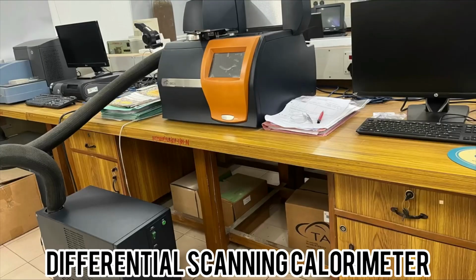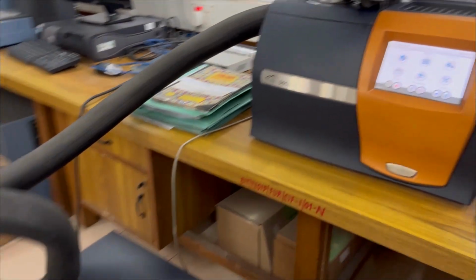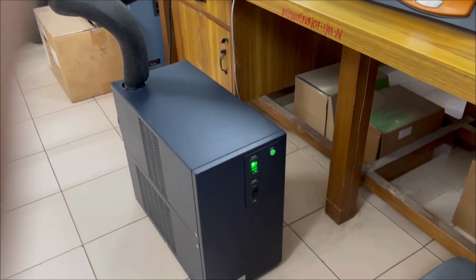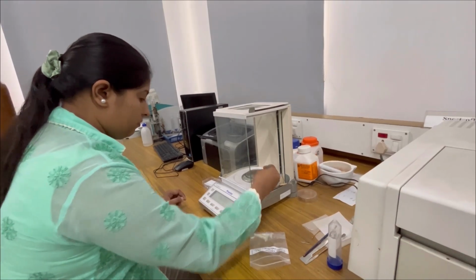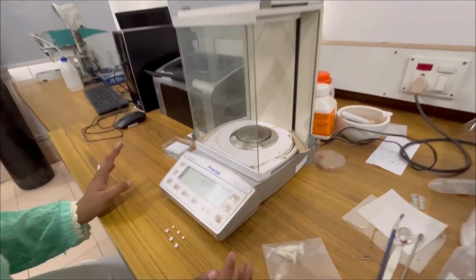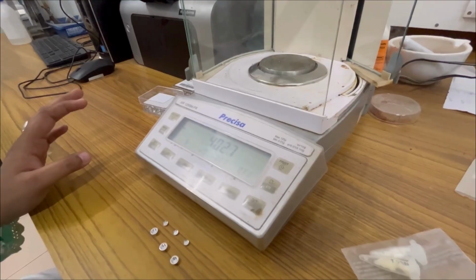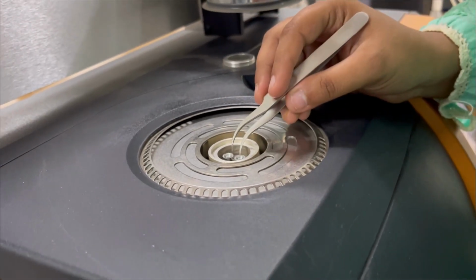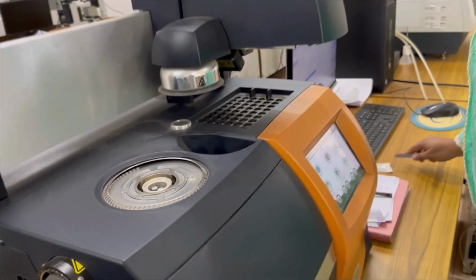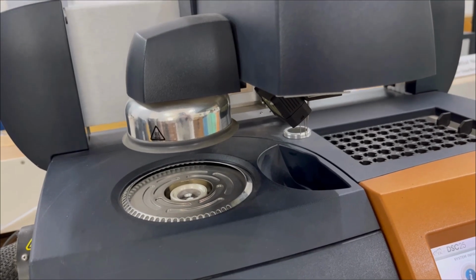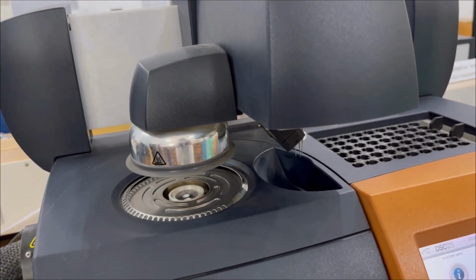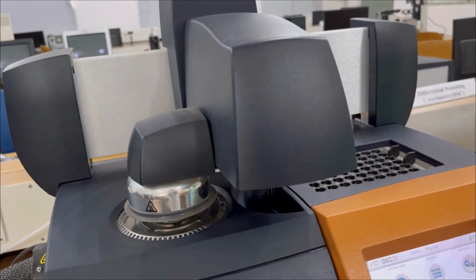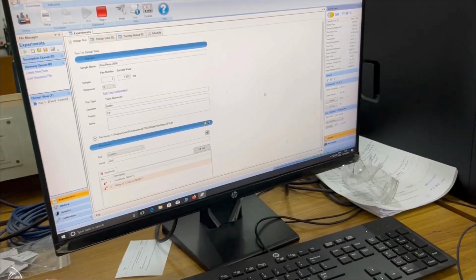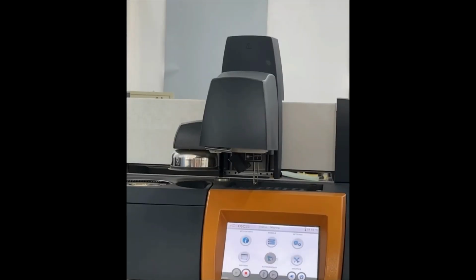This is a modulated DSC. Its make and model is DSC 25 by TA Instruments USA. This DSC measures the specific heat capacity and phase transition of various materials. The purge gas condition, heating rate, and starting and end temperature are the important parameters for this instrument. This modulated DSC is especially designed to measure crystallization, oxidation, melting, glass transition, and the percent crystallization of various materials. Instruments can be operated both manually and automatically.